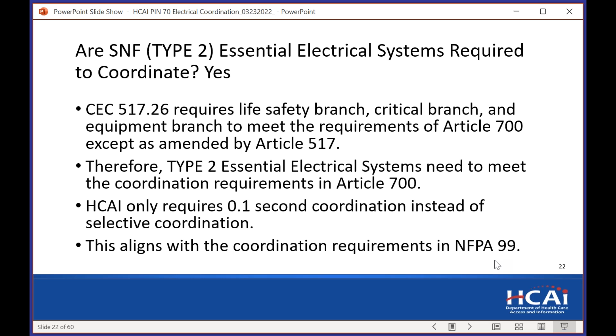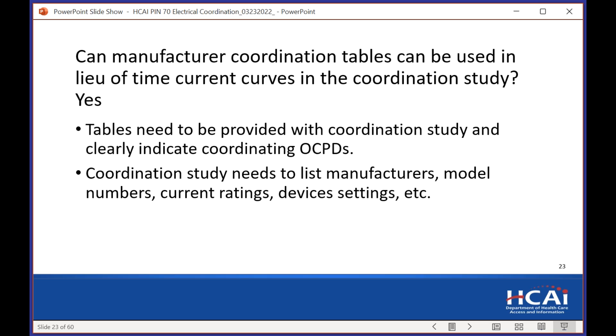Can manufacturer coordination tables be used in lieu of time current curves? And the answer is yes. There's many ways to demonstrate coordination. And if you are using the same manufacturer, you can work with your manufacturer. They do have tables. And as you clearly indicate in your study how your breakers are coordinating using this information, that is acceptable.